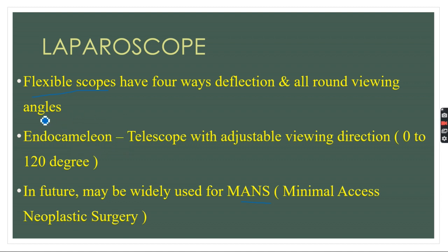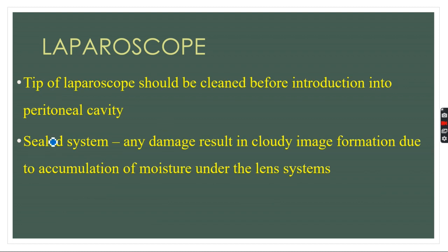There is a telescope known as the endocameleon — a telescope with adjustable viewing direction between 0 and 120 degrees. We can adjust the angle of the tip while operating. Important care points: the tip of the laparoscope should be cleaned before introduction into the peritoneal cavity every time. Also, this is a sealed system, so any damage will result in a cloudy image due to accumulation of moisture under the lens system.